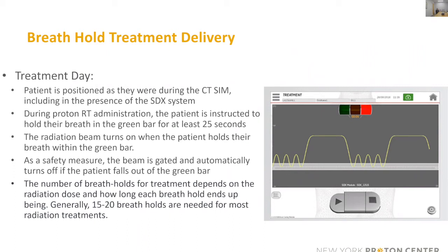And we do have an added safety feature and a quality assurance feature, which is a gated feature here at NYPC, where if the patient were to fall out of that green bar earlier than the beam is finished delivering, it will actually stop the beam. And Dr. Lin will again talk a little bit about all the quality assurance that's gone into actually being able to have that feature available.